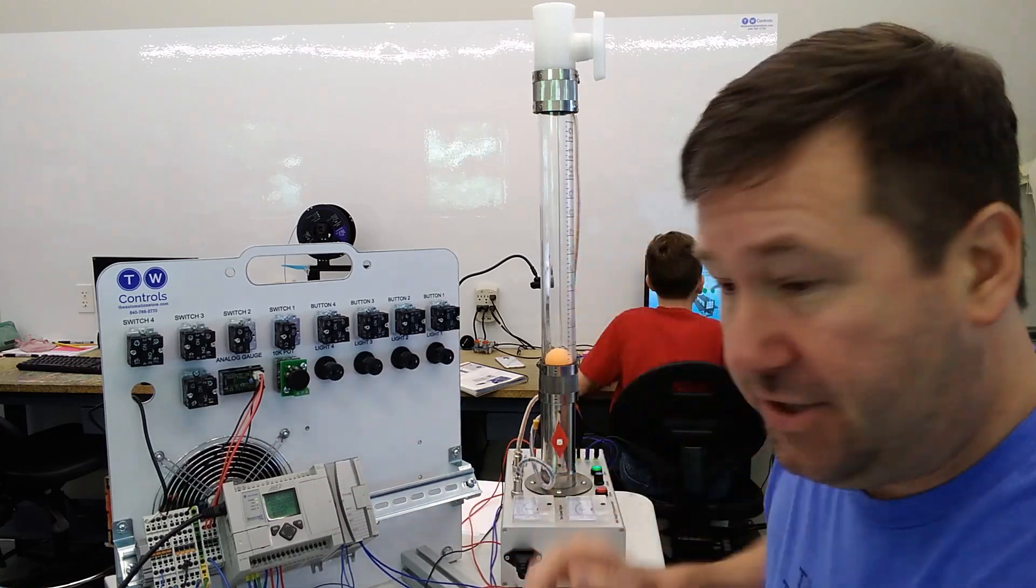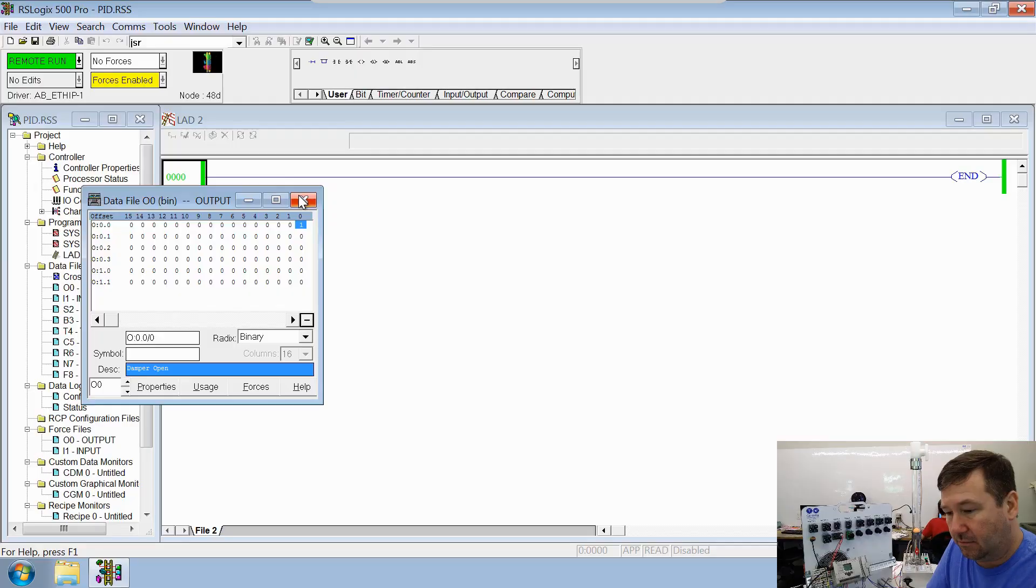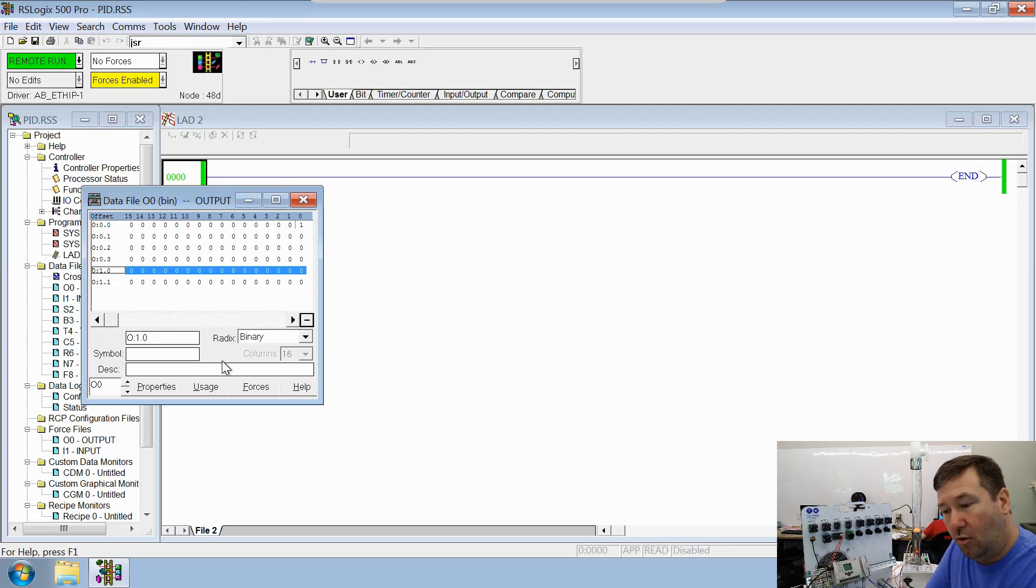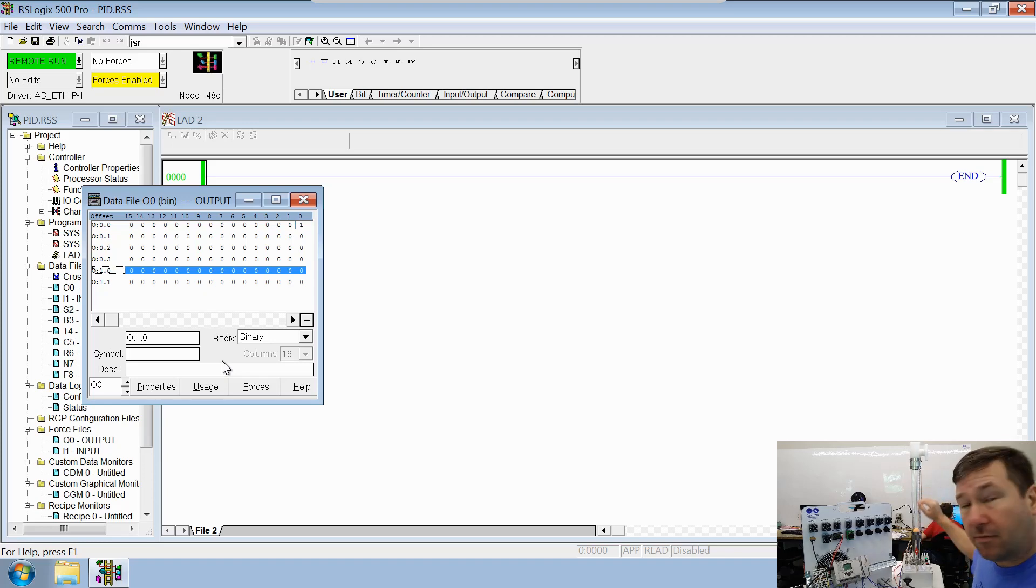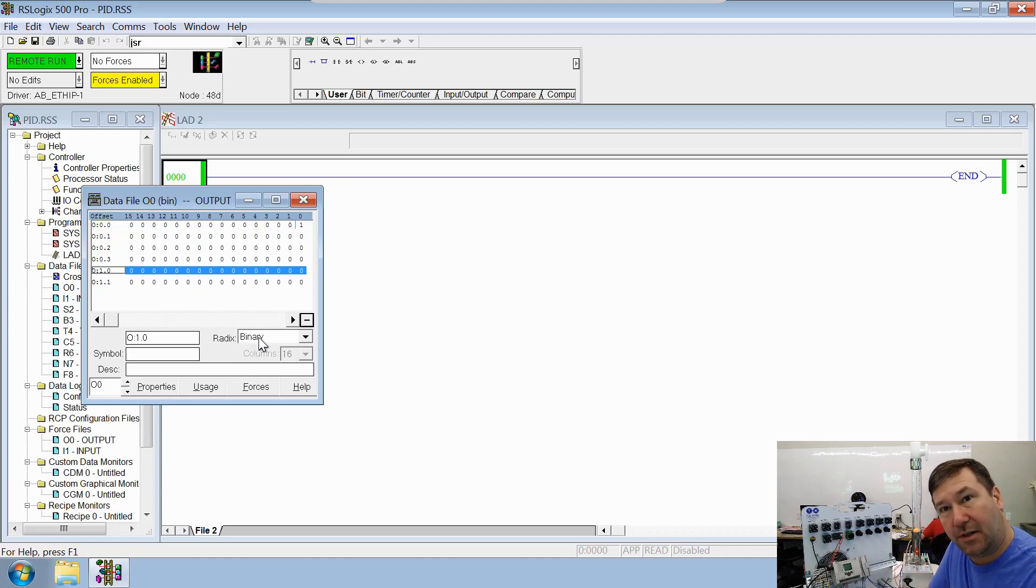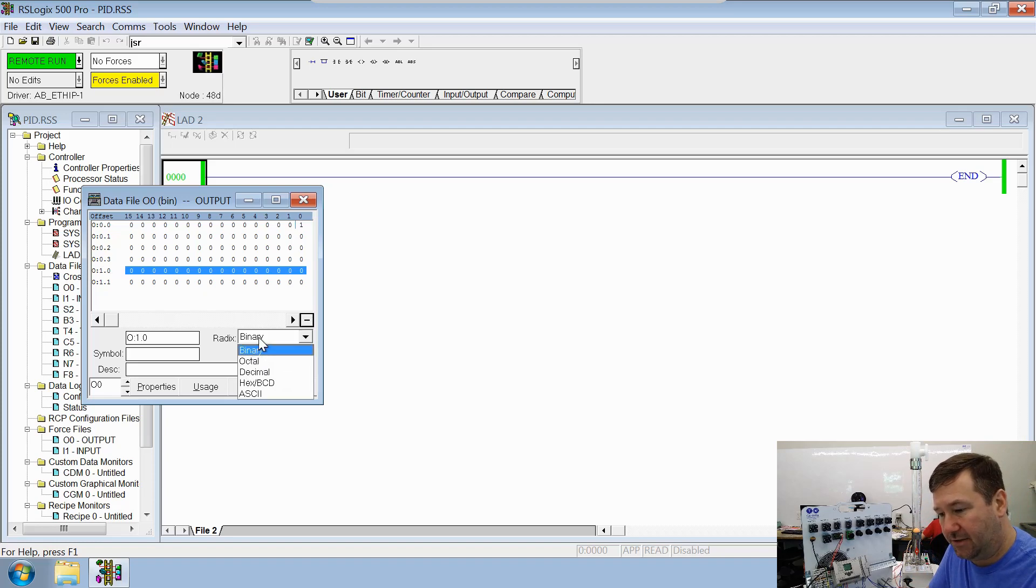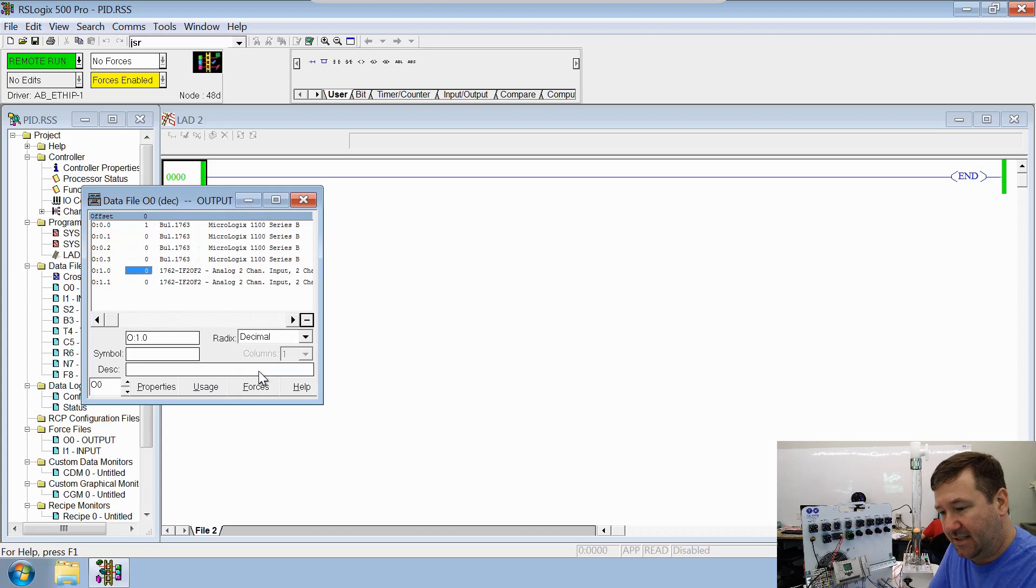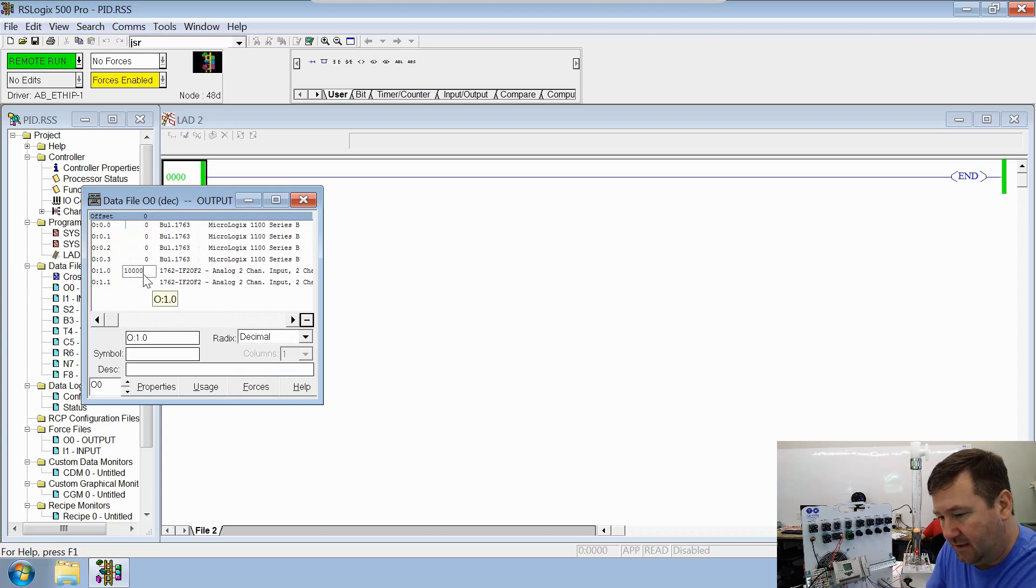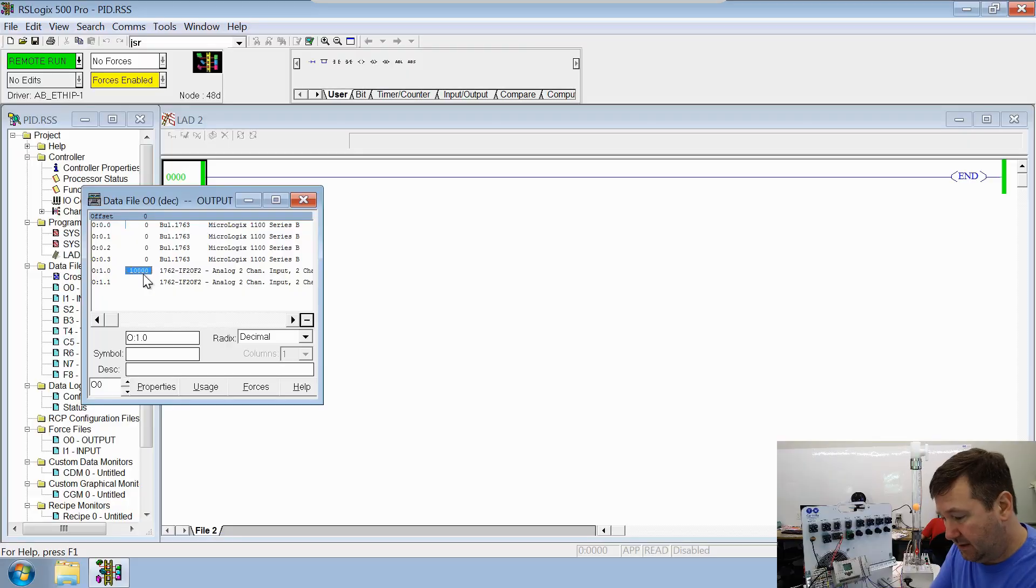Now, let's check our analogs. So right here is O colon one dot zero should be our voltage output. Now it's in binary right now, which is a little difficult when you're working with analog values. So if we hit the radix button here, then we can switch it to decimal. Let's try just putting in 10,000. Ooh, yep, it goes up.